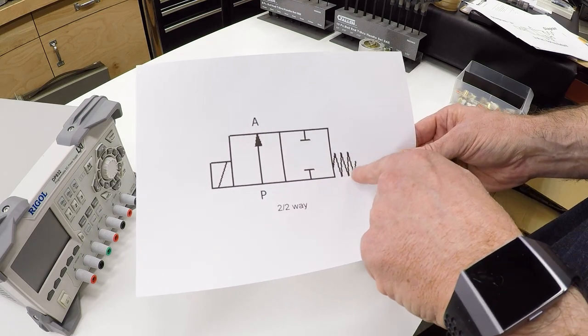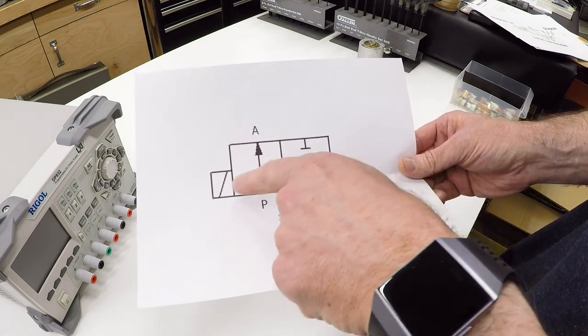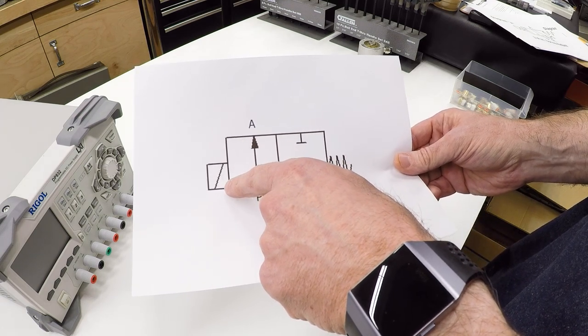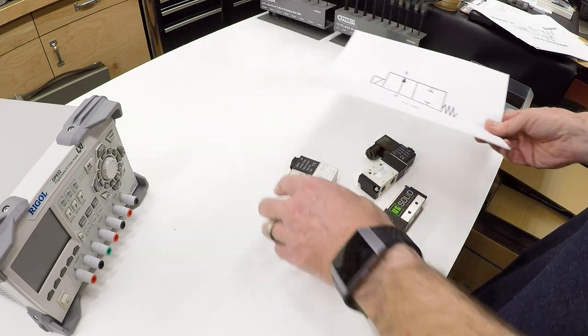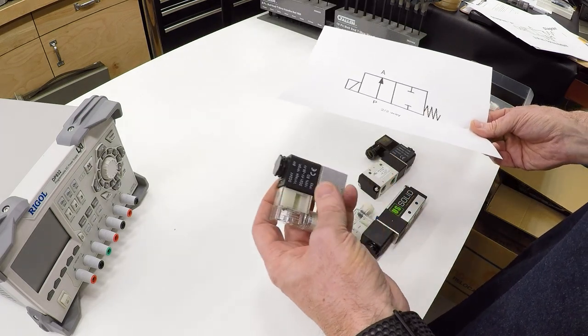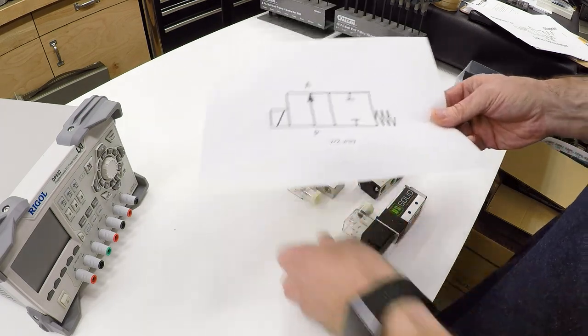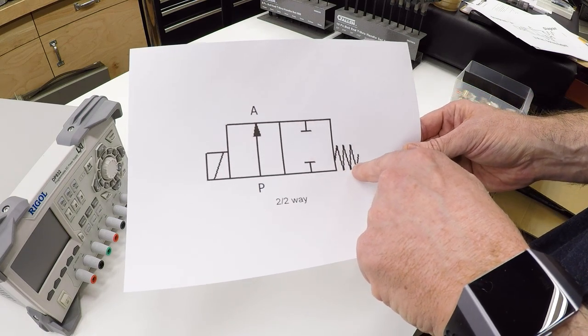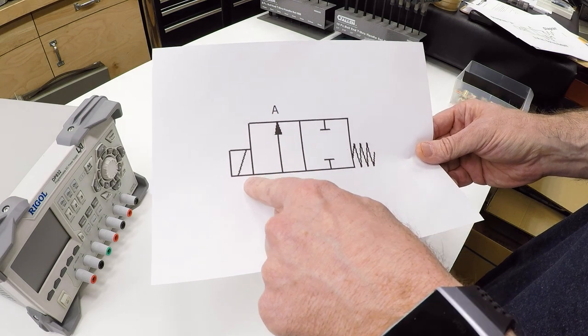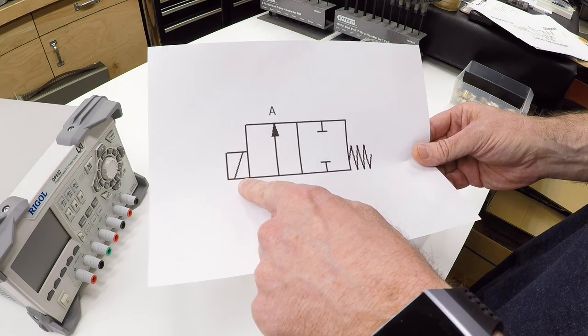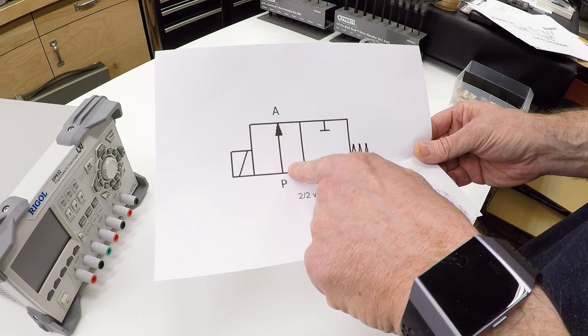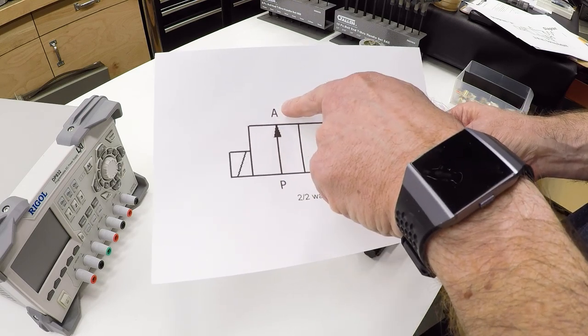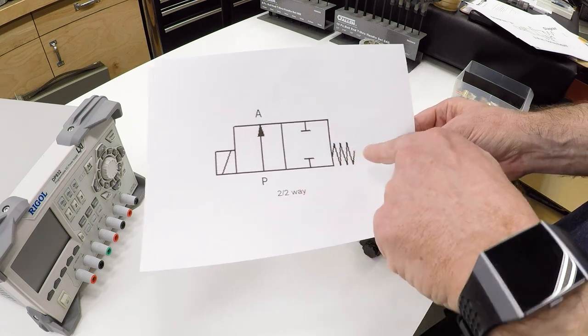The symbols on the side tell you how these different states are activated. This rectangle with a slash through it is an electric solenoid, and that's the electromagnet that is mounted here on the top of the valve. This symbol on the other side is a spring that's inside the valve. When this solenoid is active, when there's current flowing through the electromagnet, this state of the valve will be selected so that air can move from the P port to the A port.